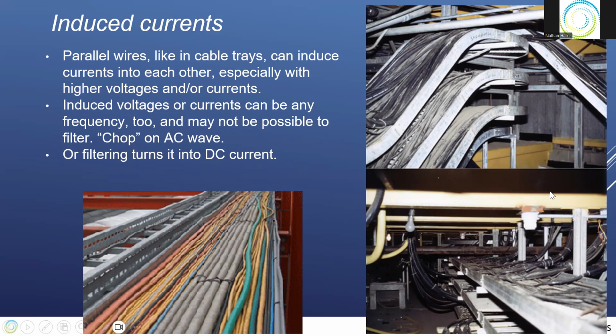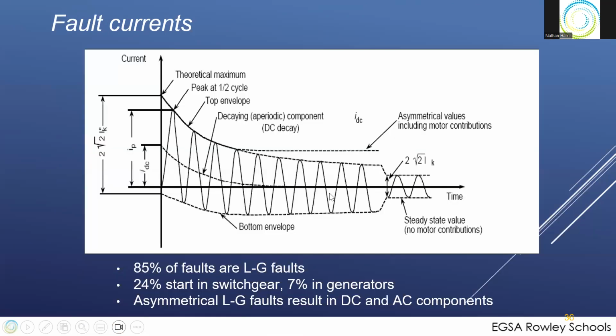So it does happen. And also when you have a fault condition, as we know, the faults are common. Usually 85% of them are line to ground faults. 24% start in the switchgear and 7% in the generators. The rest of them are out in the distribution system somewhere.